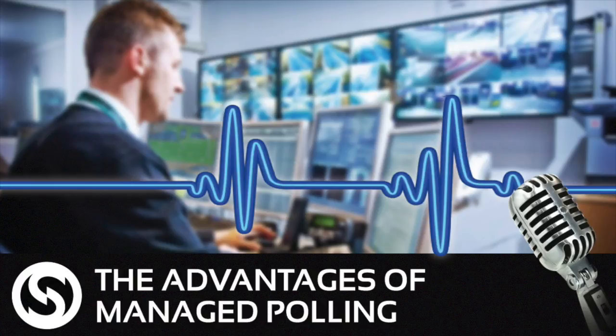So even when, let's say, we've lost Telstra and Optus IP paths, we can then go, okay, well, one of them still had a voice channel. Let's go to the voice channel, make a poll or voice call alarm. And that way we've got 4 fully independent functioning paths to talk on. And this is in a day, Simon, when the majority of IP communicators are turning their voice channel off.